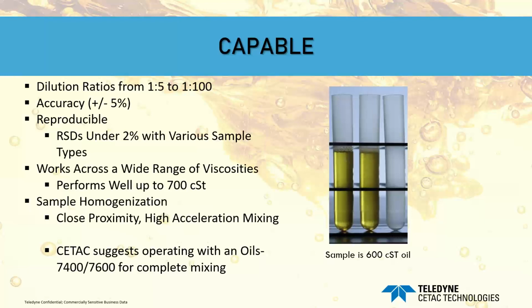It also mixes the samples as it dilutes, and here in the graphic you can see the dilution of a 600 centistoke sample. You can see it deposit the oil sample, and then it follows it with a high velocity shot of diluent, which mixes the sample. If you want to ensure the best possible homogenization, we do recommend pairing the APS 7450V with one of our Oil 7400 or Oil 7600 stirring auto samplers. We'll talk about them a little bit later.